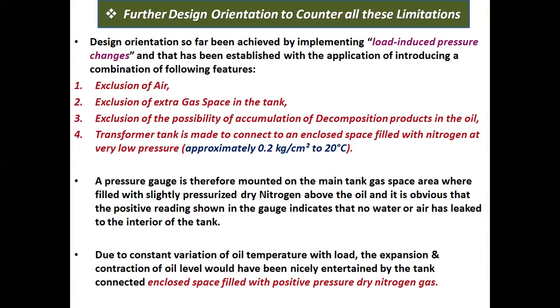A pressure gauge is mounted on the main tank gas space area, which is filled with slightly pressurized dry nitrogen above the oil, and it is obvious that a positive reading shown on the gauge indicates that no water or air has leaked into the interior of the tank. Due to constant variation of oil temperature with load, the expansion and contraction of the oil level is nicely accommodated by the enclosed space connected to the tank, filled with positive pressure dry nitrogen gas.